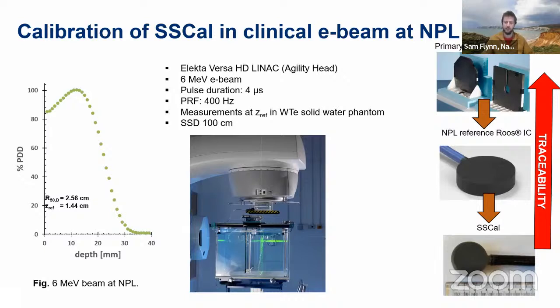So this allowed us to get a Gray per Kelvin calibration factor of the secondary standard calorimeter. This is odd for a calorimeter because normally you use them and you realize dose in its absolute form. There's no calibration, but here we are converting it from one to the other. At this point, we have a calibrated calorimeter. We need to do some tests with it. We need to prove it works.